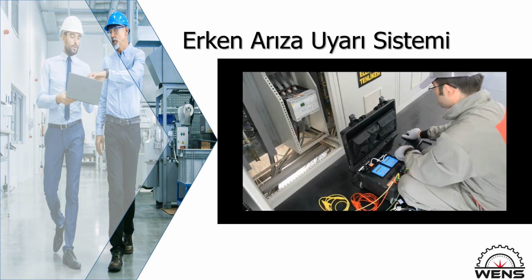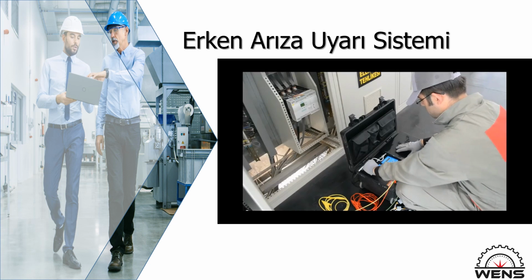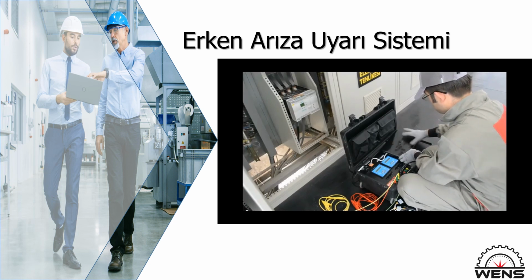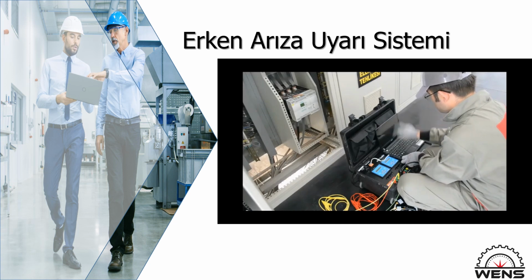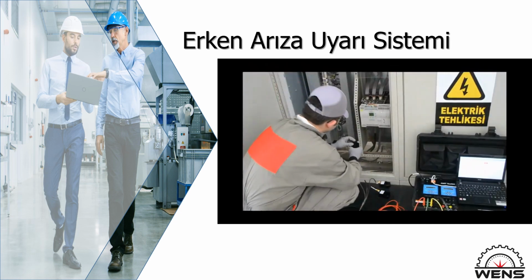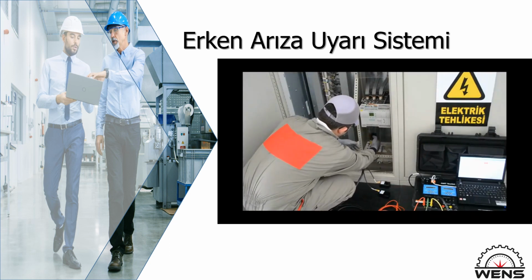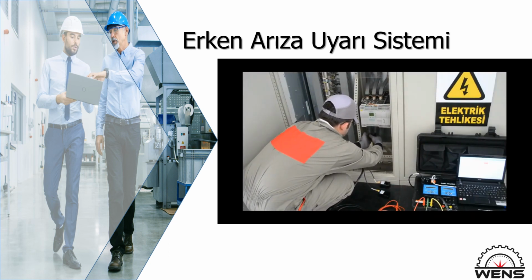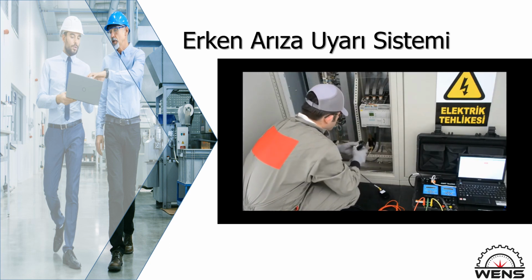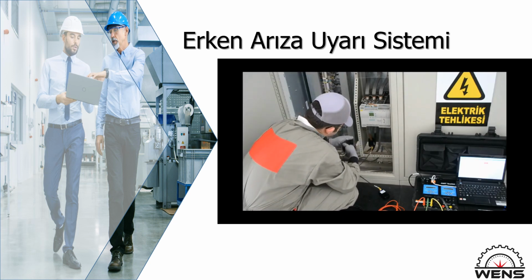It collects data for 30 minutes from motor-driven equipment and saves to SQL database to generate an instant condition assessment report. The total duration of the test is approximately 45 minutes to 1 hour, including the installation, stopping and starting the motor, data acquisition, and dismantling processes. At the end of the testing period, Toolkit generates a condition assessment report, which indicates existing faults in the system, recommended corrective action, and the effects of these faults on energy efficiency.